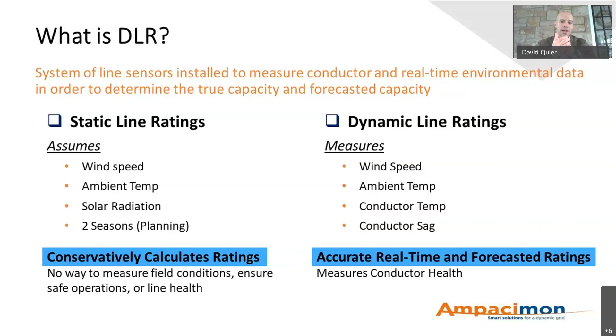One thing we learned working with Ampacimon: when you look at the static rating for a line and then adjust upward based on accurate ambient temperature, the rating increases by a good amount for most of the year. But it's really when you add wind data that the rating increases significantly more. That's something we really appreciated from working with Ampacimon.